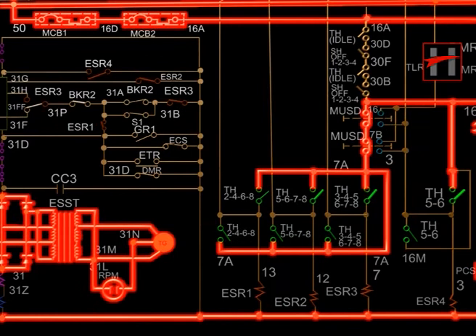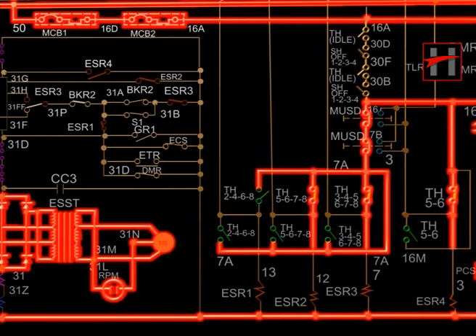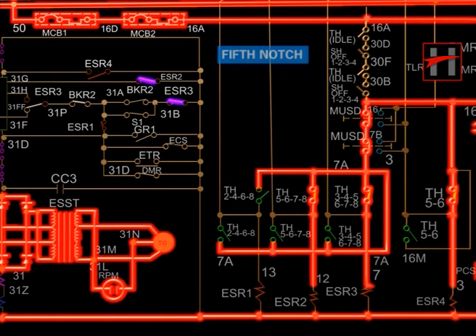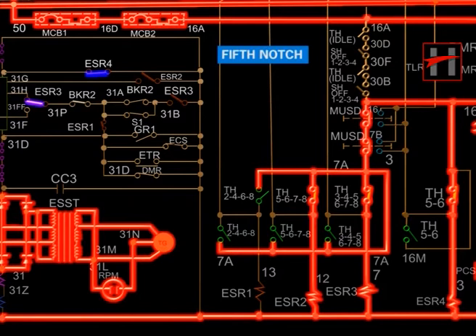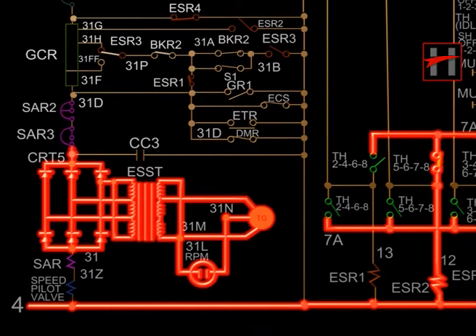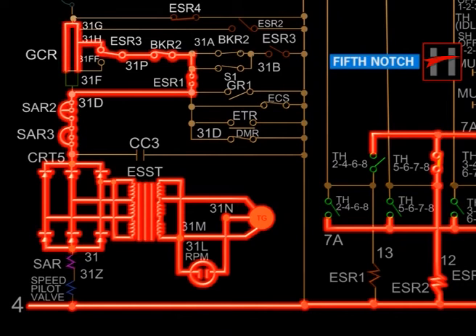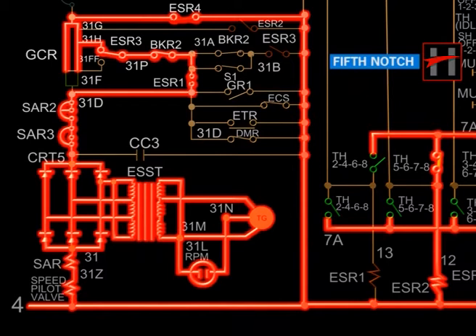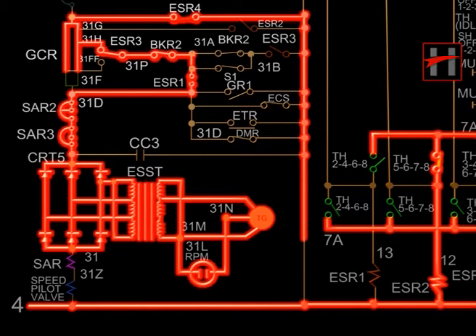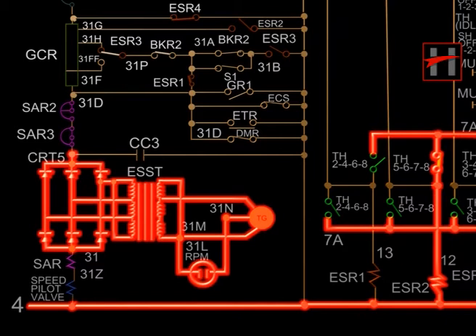In the fifth notch position, ESR-2, ESR-3, and ESR-4 get energized. The normally closed interlock of ESR-1 closes due to de-energization of ESR-1. The interlock of ESR-3 changes position from 31F to 31FF. The normally open interlock of ESR-4 closes and the normally closed interlock of ESR-2 opens. The rectified output of the tacho generator flows through CRT-5, SAR-3, SAR-2, cable 31D, interlock of ESR-3, interlock of ESR-1, BKR-2, ESR-3, cable number 31FF, GCR, cable number 31G, interlocks of ESR-4, and completes its path with cable number 4, speed coil of pilot valve, cable number 31Z, SAR coil, and cable number 31.